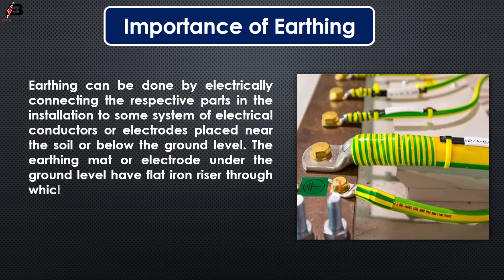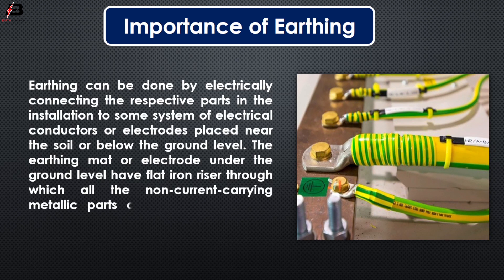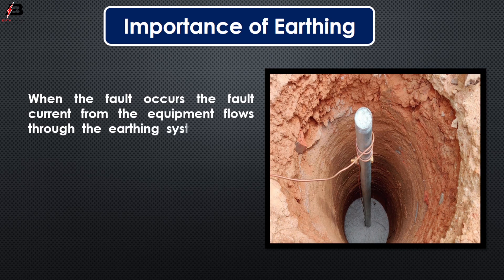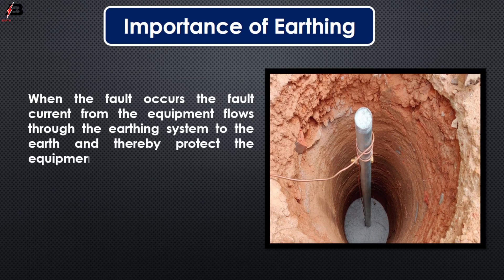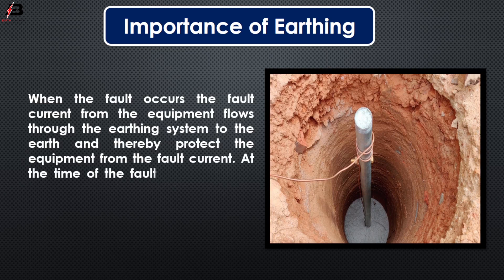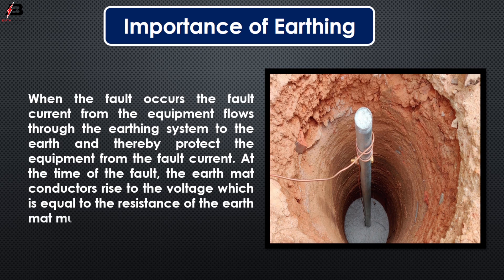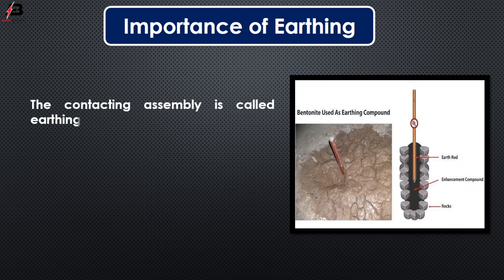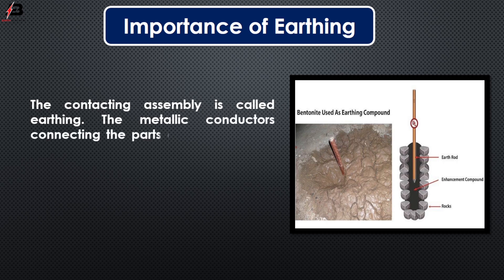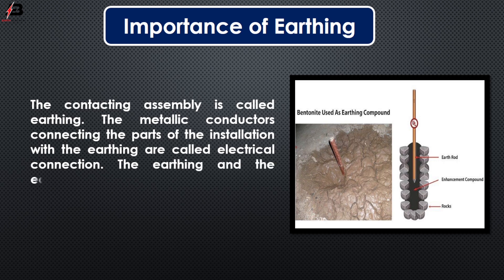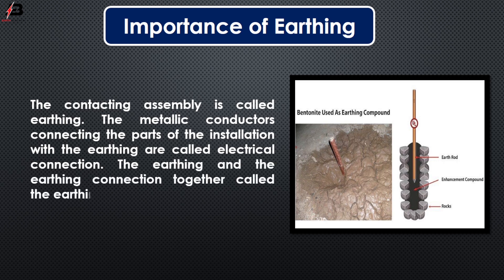Flat iron riser through which all the non-current carrying metallic parts of the equipment are connected. When a fault occurs, the fault current from the equipment flows through the earthing system to the earth, thereby protecting the equipment from the fault current. At the time of fault, the earth mat conductor rises to a voltage equal to the resistance of the earth mat multiplied by the grounding fault current. The contacting assembly is called earthing. The metallic conductors connecting the parts of the installation with the earthing are called electrical connections. The earthing and the earthing connection together are called the earthing system.